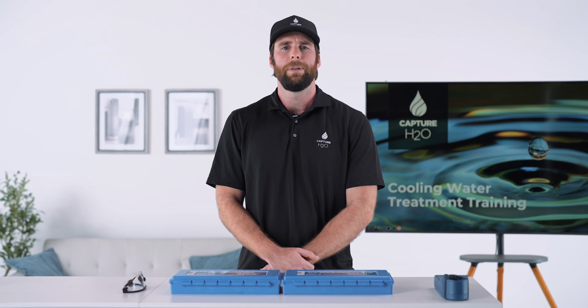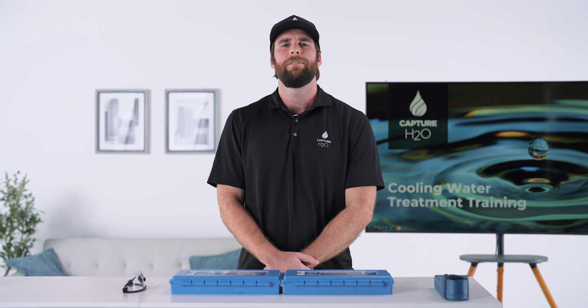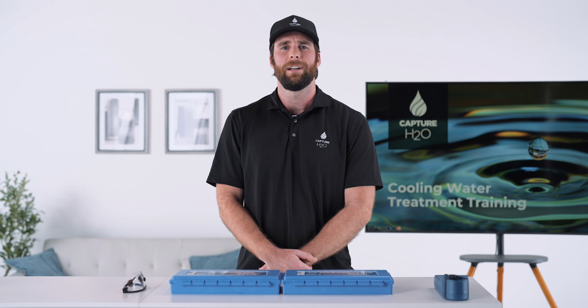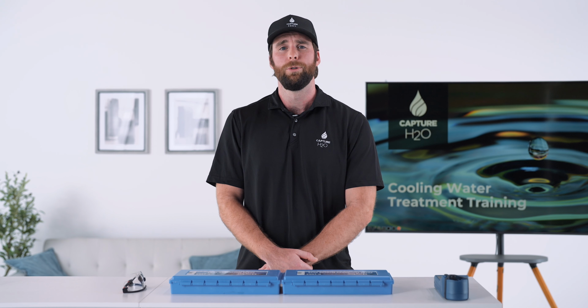It's important that we acknowledge all alarms, but a low pressure alarm could mean that your tower is not receiving makeup. Failed regeneration means that the softener did not receive its salt slug. This will lead to overrunning of the softener and therefore hardness breakthrough. In the event of a high conductivity alarm, this means that the blowdown is not receiving flow. You will want to check your blowdown valve to ensure that it is functioning properly. Low conductivity alarm means that you are losing water, either by way of overflow or a leaking blowdown valve, or potentially excessive drift and splash out.